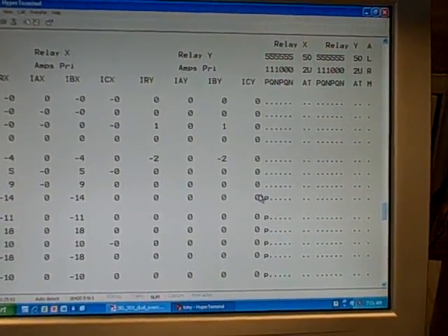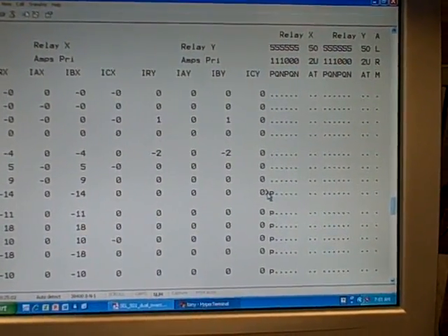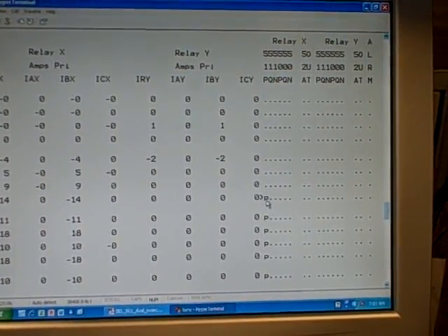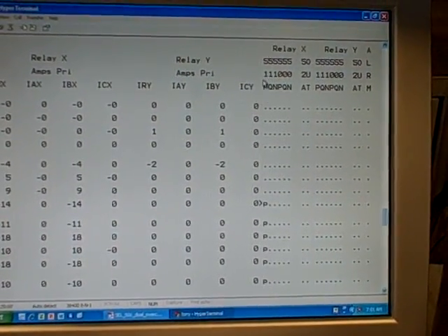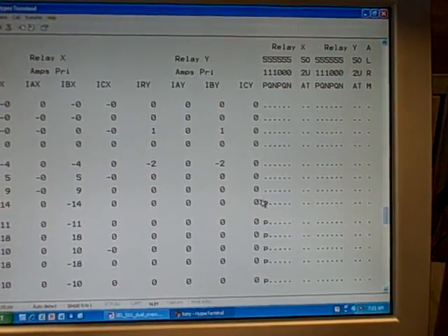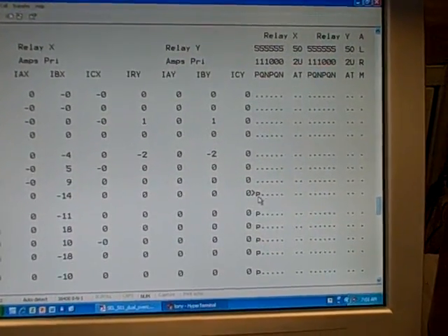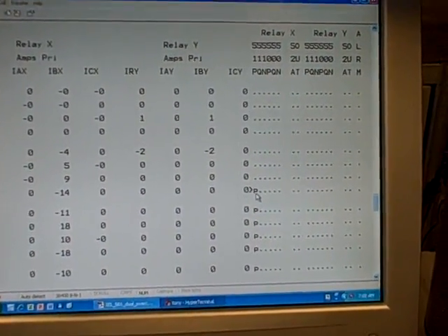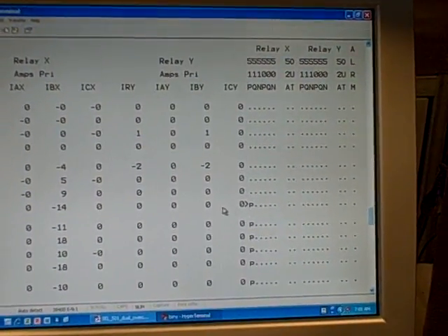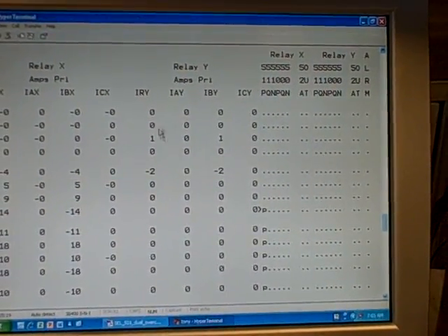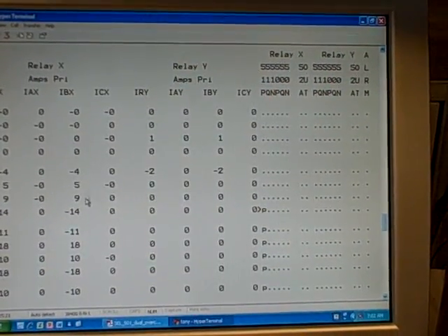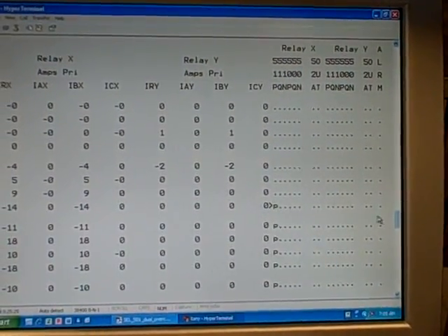Right here you see a greater than symbol, then the letter P. That is indicating that the phase element, 51P, the time over current phase element has begun to pick up. In that moment in time, we've exceeded the pickup value for that relay element. You notice in this first cycle, no current is flowing. In the second cycle, we do have current, so that is when the vacuum cleaner is first turned on.